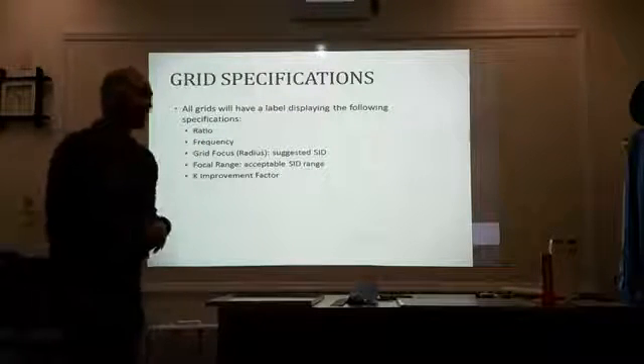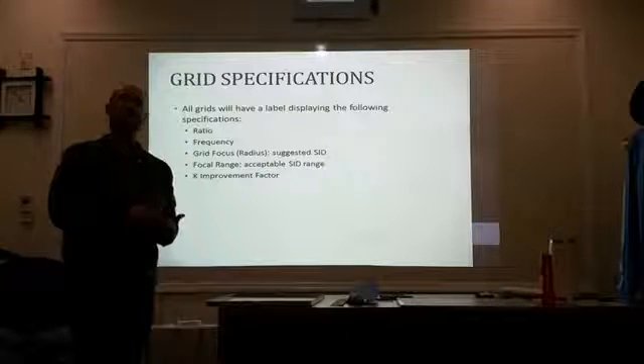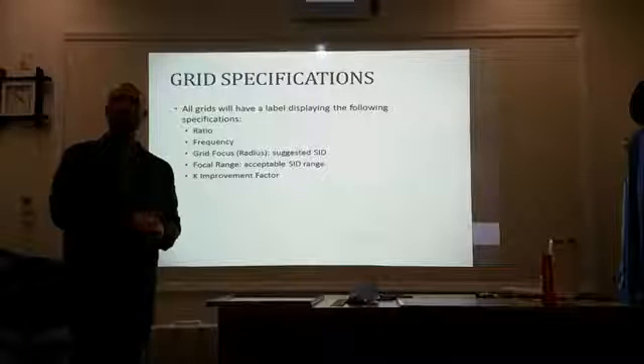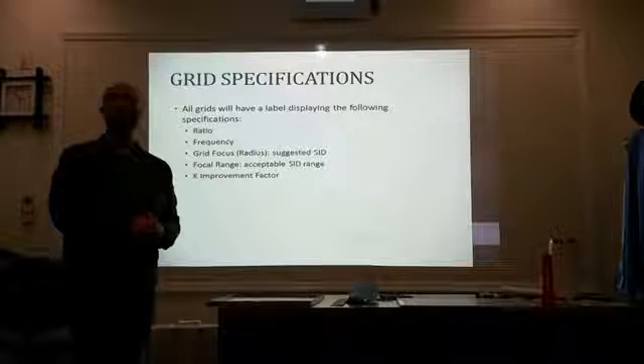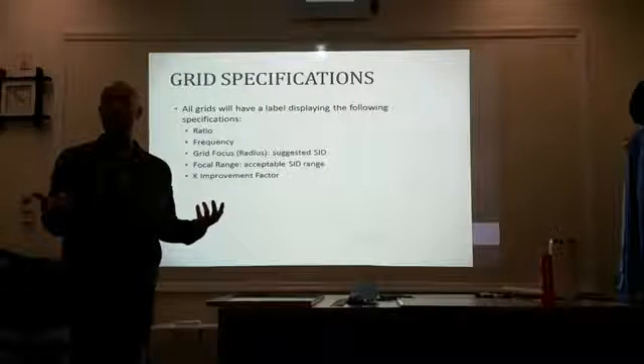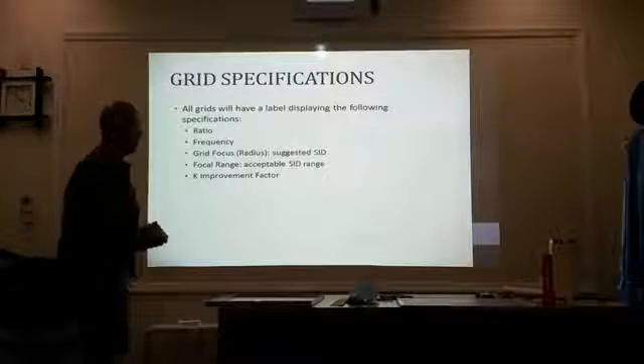So again, with higher grid ratios, it's good, but higher technical factors, narrow margin of error. With lower grid ratios, we don't bump up our technical factors that high. Our resulting image should be good, but not as great as a higher grid ratio.